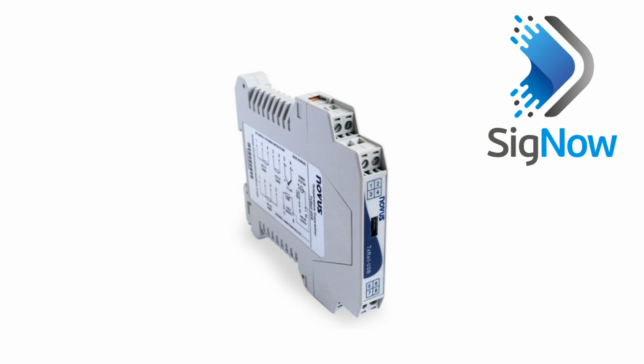The TxRail-USB connects to a computer's USB port using a standard USB cable with a micro Type B connector. For configuration, the TxRail-USB can be powered directly from the USB port. However, when used in production, you should connect the TxRail-USB to a separate power supply, since the USB connection won't provide enough power to drive the output of the TxRail. It's also important to note that although the TxRail-USB uses a standard USB cable, the cable must have both power and data lines for it to be compatible with the TxRail-USB. It's also worth mentioning that you should install SigNow before plugging the TxRail-USB into your computer.